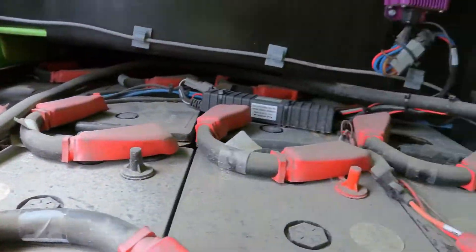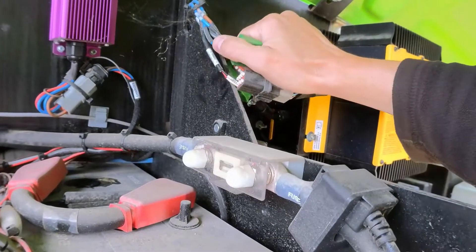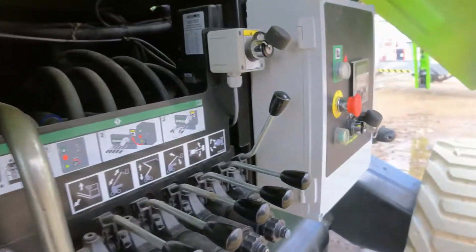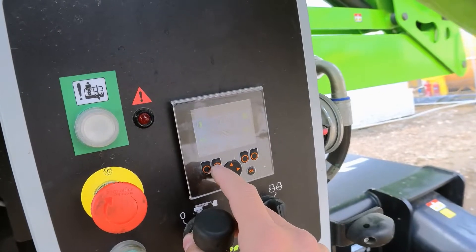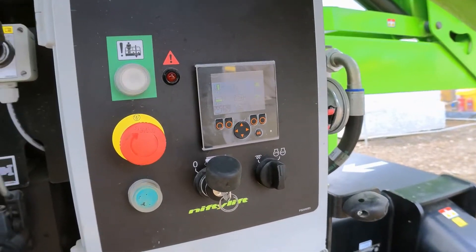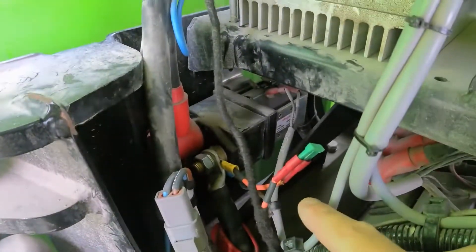What I'm going to do now is go through the wiring and check all the grounds to make sure there's no further problems. Then we'll test the machine and see how it goes. If I can get it to fail again I'll continue fault-finding; if not, we can say it's fixed. But I'm wondering why that fuse blew.